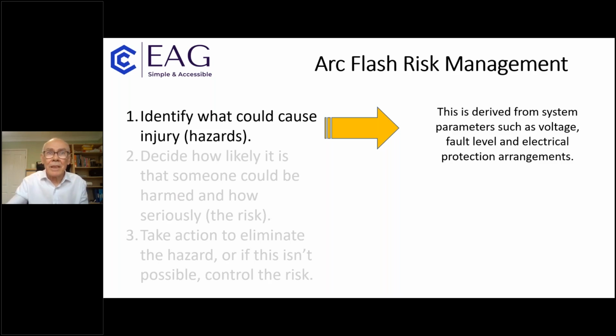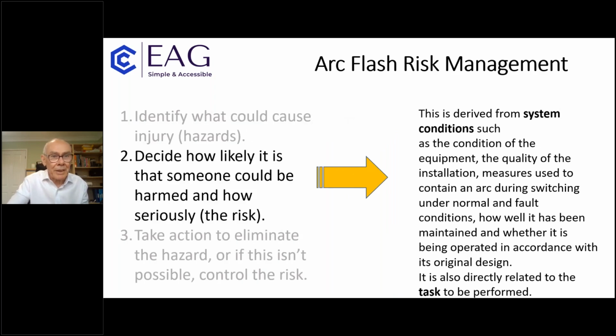We're firstly asked to identify what could cause injury, in other words, the hazard. When we look at arc flash, in the first instance, we look at system parameters such as voltage, fault level and electrical protection arrangements. The next step is deciding how likely it is that somebody could be harmed and how seriously, in other words, the risk. This is derived from system conditions such as the condition of the equipment, the quality of the installation, measures used to contain an arc during switching under normal and fault conditions, how well it's been maintained, and whether it's been operated in accordance with its original design. It's also directly related to the task to be performed, which is an important consideration.